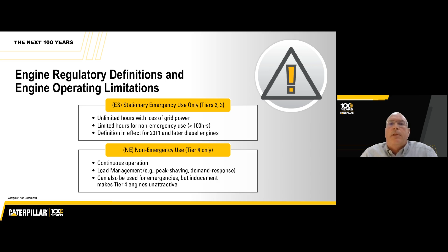Stationary emergency use engines can run unlimited hours when there's an actual loss of grid power. These engines may need aftertreatment to meet site-specific emissions, depending on where they're installed, which we'll talk about in a few minutes. But typically, these engines don't come from the factory with aftertreatment. On the other hand, non-emergency engines, or Tier 4 certified engines, are designed for continuous operation or load management, and typically have aftertreatment added directly from the factory. Stricter inducement requirements can make these engines less attractive for some sites.